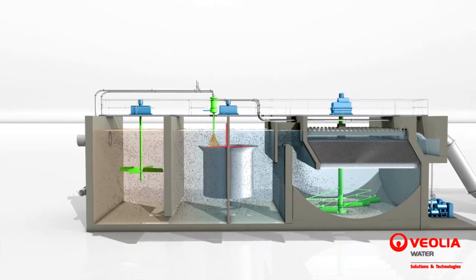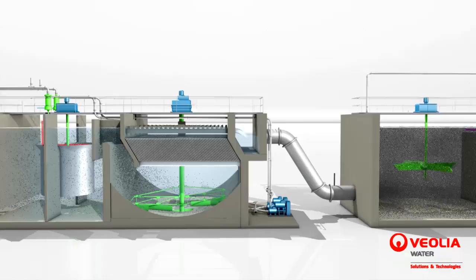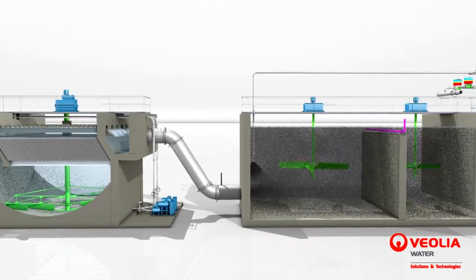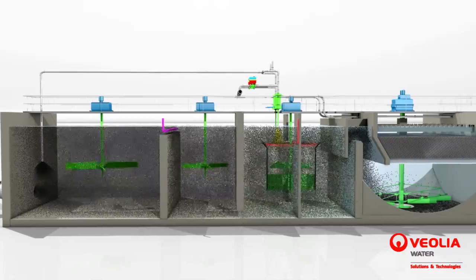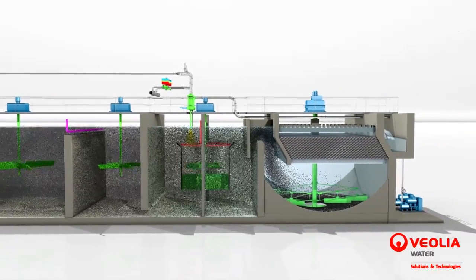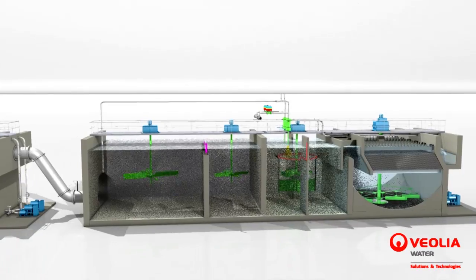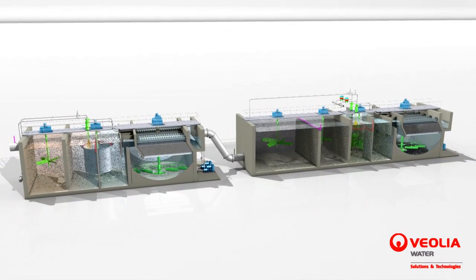consumption of activated carbon. The first Actiflo unit consists of typical chemical clarification for the removal of suspended solids and flocculable compounds, followed by an Actiflo Carb polishing unit for the physical adsorption of non-flocculable compounds. The unique Actiflo Twin Carb design is especially suited for the treatment of highly polluted waters, making it possible to remove up to 90% of the total organic carbon with influent levels up to 15 milligrams per liter or greater.